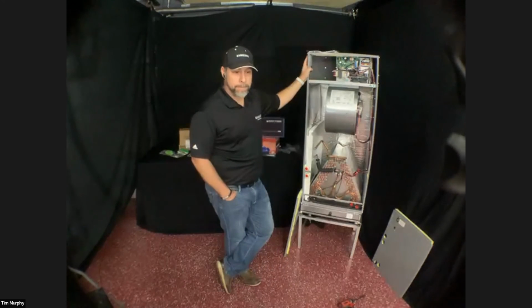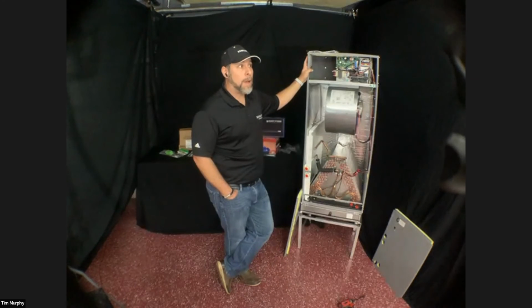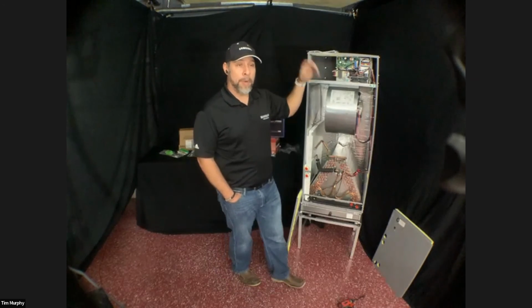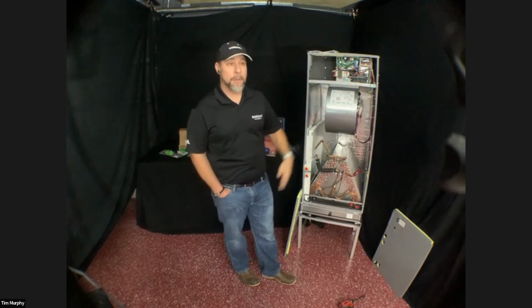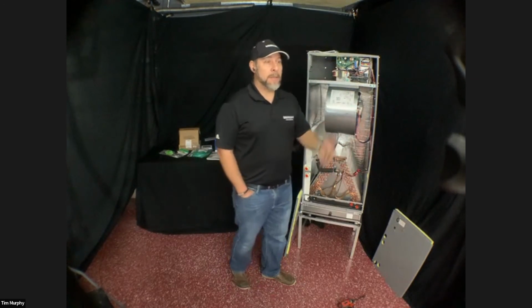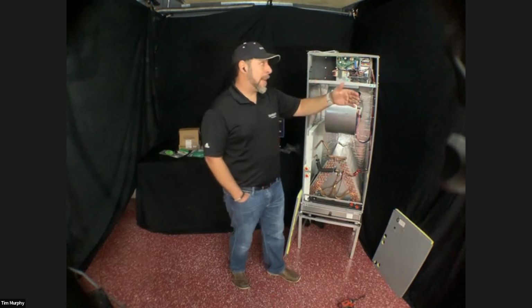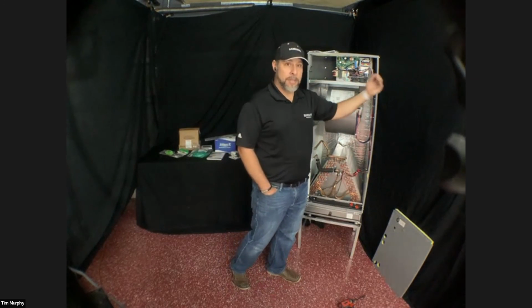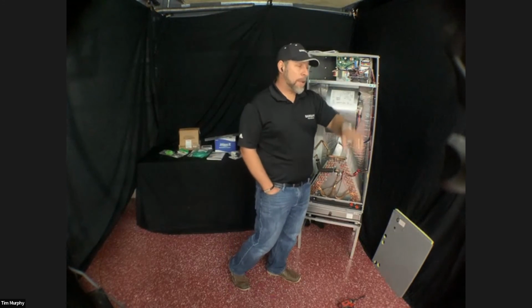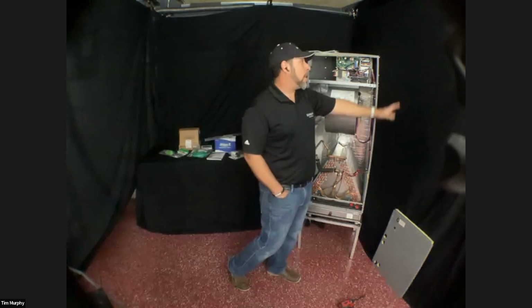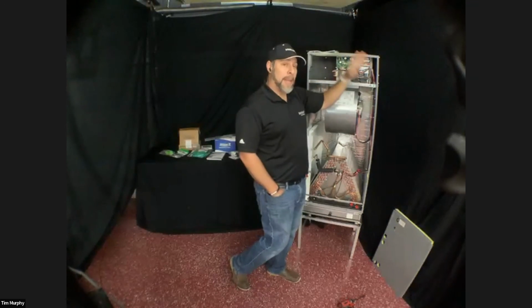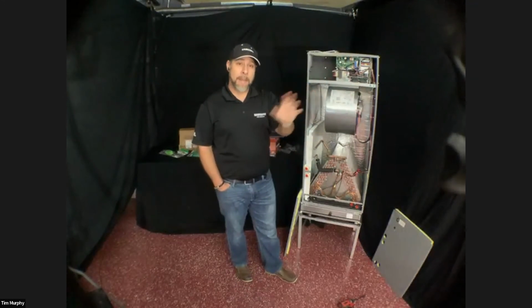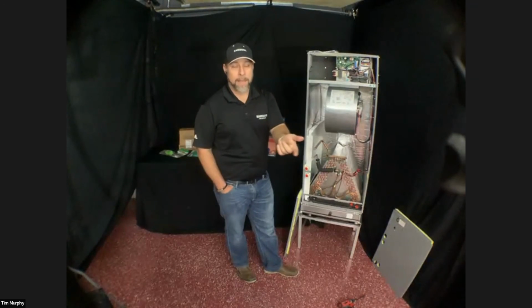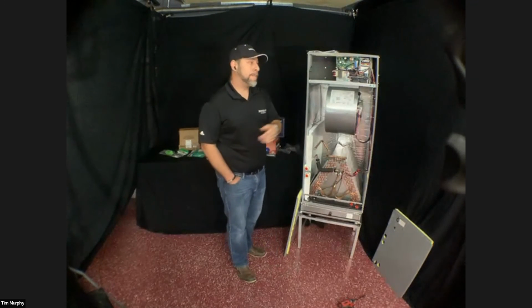John Damon asks, only one breaker if no heat strip? Well, yes, you only need one breaker, and that'll be at the condenser. That's all you would need. If this is a new install, then you would only need to supply a breaker. Now you can put a disconnect, because of course, code, you're still going to need that disconnect. You could still run that line voltage to a disconnect in the air handler closet and then to the condenser. But yes, you will only need one breaker, and that max amp information will also be in the submittals, whether you use the app or you go to samsunghvac.com.